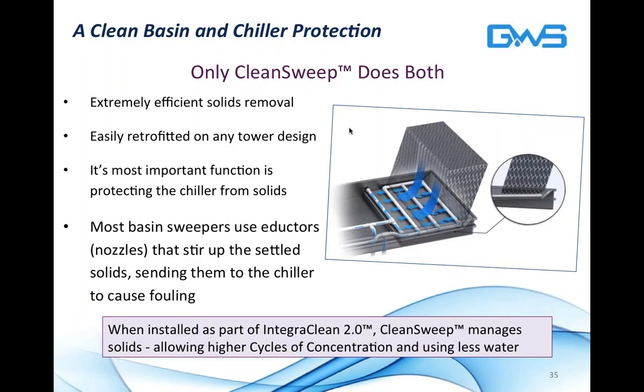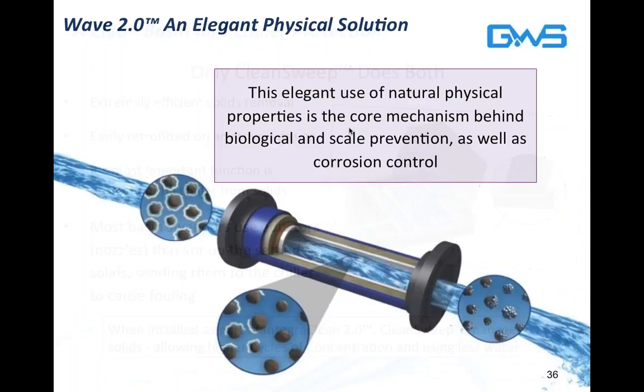It's easily retrofitted into any tower design, and it prevents solids from collecting at your heat exchanger. Those nozzles that stir up settled solids just send them right back into the chiller, entrained in the water. When installed as part of IntegraClean, CleanSweep manages these solids and keeps the basin cleaner, without giving you an energy penalty from solids at your heat exchanger.